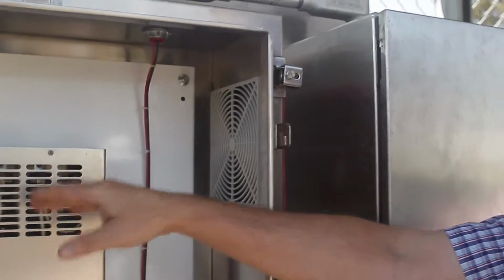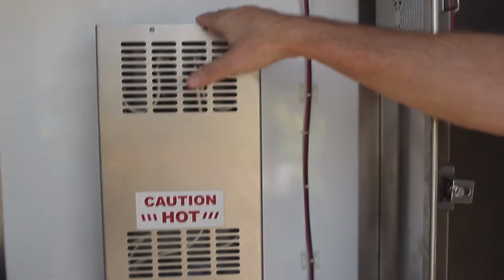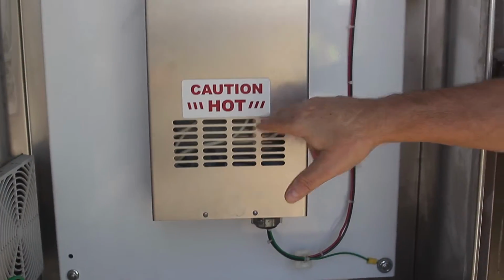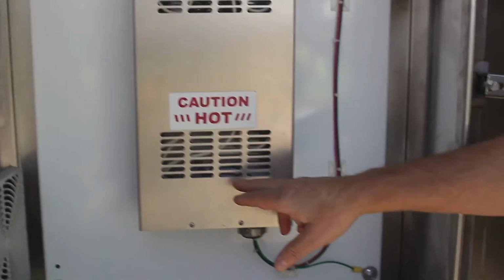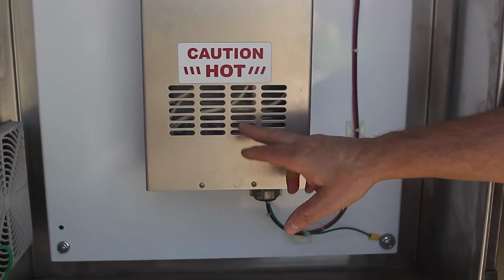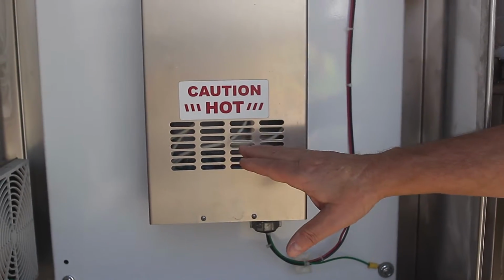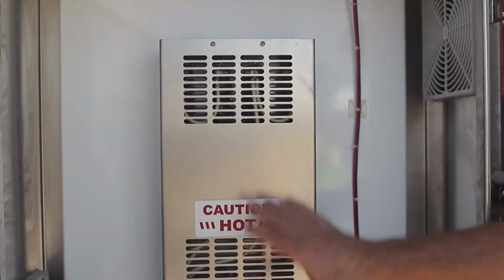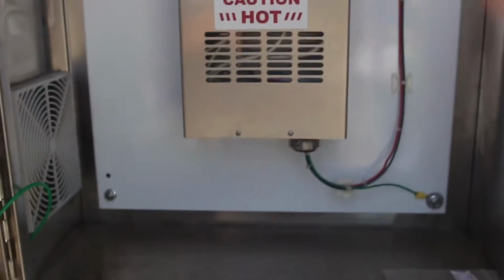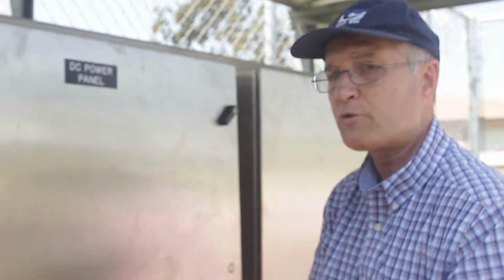But when the batteries are full, this will warm up and may become hot, so that's why there is a warning. We actually changed the wiring for 24 volts from 12 volt internally. The electrician has finished that already, so it's already connected, and I feel even a little bit of warmth already coming from this. So I can touch it, but it's warm already. So it's already starting to divert some of the energy. So now we'll go to the telemetry panel.